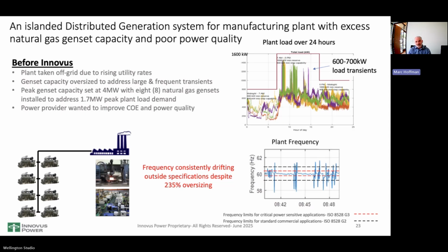This application really proved what we call our power bridge feature, which integrates solar and wind. If you look at this load profile, it's far more aggressive and problematic than any volatility associated with solar and wind. You can see the impact on frequency in the lower right when they hit these high volatile load changes, literally a 700 kilowatt load change within seconds that would then disappear. This was happening every day, and you can see the concentration. Highly problematic, especially with a natural gas genset, which is slow to respond.